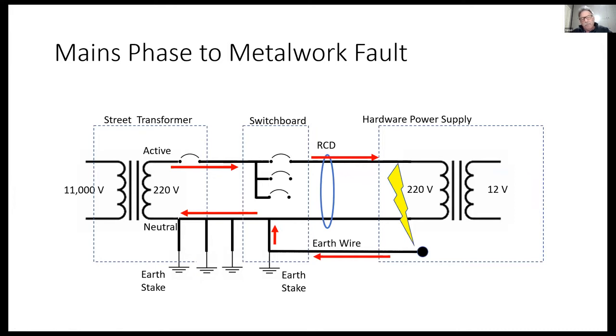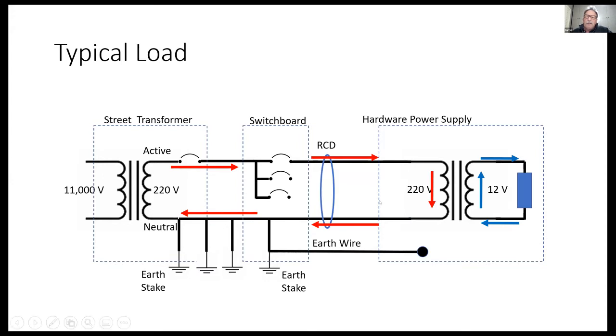Trip the circuit breaker. So that's the sort of thing we need to do: draw these sorts of circuits out to figure out the question, where is the current flowing and what connections do I need? So from a safety point of view, this earth wire was bonded to the metalwork of the hardware. It's not there for the function. Go back a page here. The function of the equipment is this red circuit. The earth bond does nothing. There's no current flowing in this earth bond wire when the equipment's functioning normally. So separating that question right at the start, where we said, look at the function of equipment versus the safety of it: you don't need the earth bond there for function, but you do certainly need it there for safety.